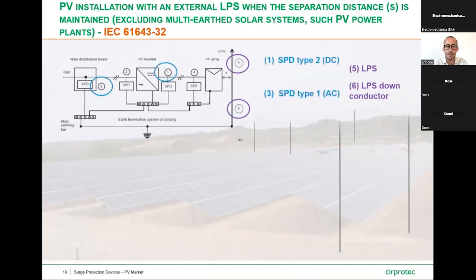Then the standards state as mandatory to install an SPD in the location 1, close to the inverter in the DC side of the PV installation. That should be an SPD type 2. And then it should be installed in the location 3, in the AC side of the PV installation, an SPD type 1.